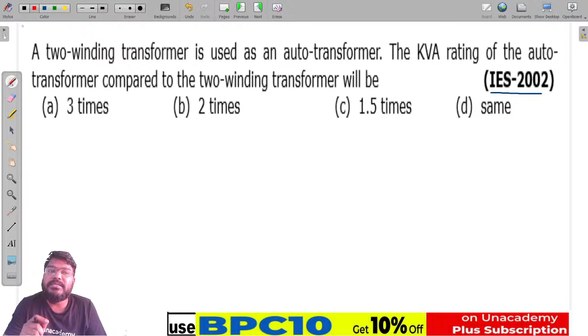How do we solve this? If you know the k value, this is very easy. We know that kVA rating of auto transformer is equal to 1 over 1 minus k times of the kVA rating of the two winding transformer.